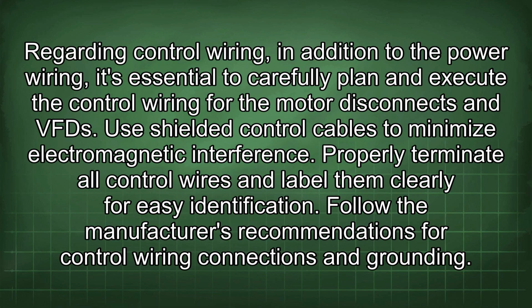Regarding control wiring, in addition to the power wiring, it's essential to carefully plan and execute the control wiring for the motor disconnects and VFD. Use shielded control cables to minimize electromagnetic interference. Properly terminate all control wires and label them clearly for easy identification. Follow the manufacturer's recommendations for control wiring connections and grounding.